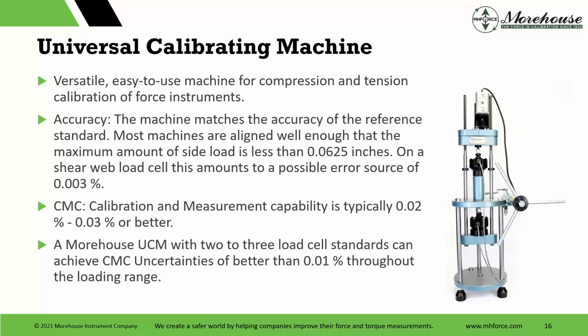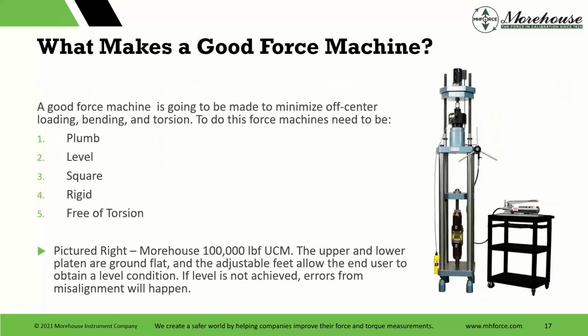The benefit of 1 standard versus 2 is doing a full calibration without changing standards, and that reduces the time. If you're willing to spend more money on standards and more time per calibration, you can drill that number down. Most people find that happy medium, again, around 0.03%. With 2 or 3 load cell standards, more than likely 3 to 4, it can be better than 0.01%.